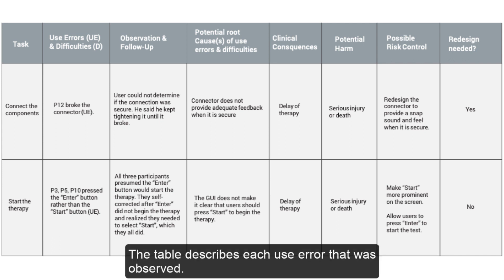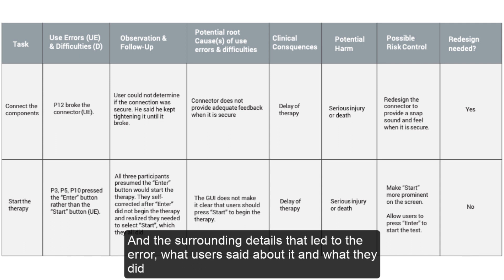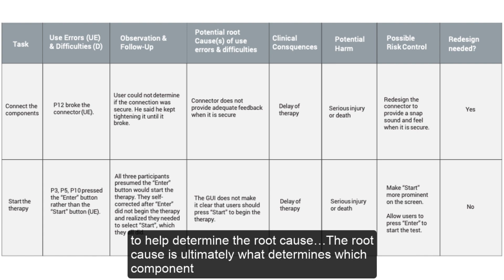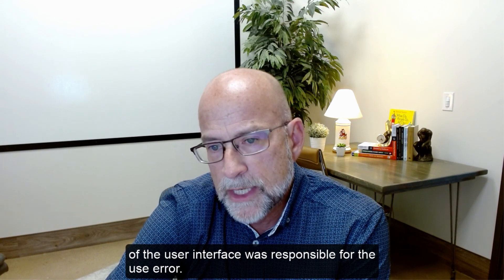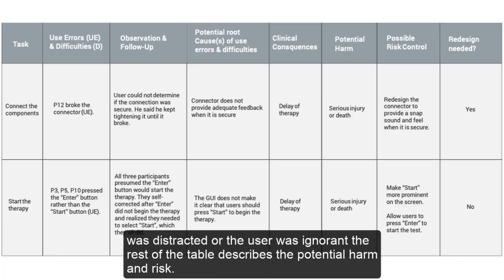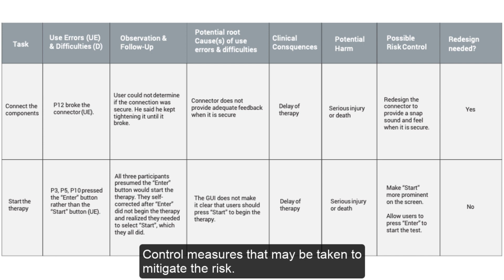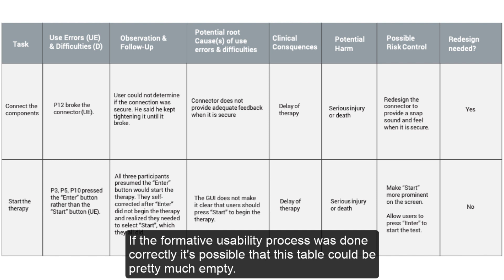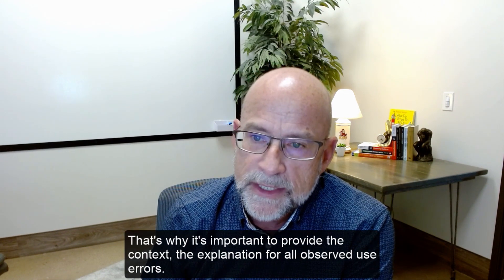Performance, knowledge, and qualitative data are analyzed and compiled in a detailed results table. The table describes each use error observed and the surrounding details — what users said and did — to help determine the root cause. The root cause determines which component of the user interface was responsible for the use error. The root cause should never be something like 'the user wasn't paying attention' or 'the user was ignorant.' The table also describes potential harm, risk, and control measures to mitigate the risk. If the formative usability process was done correctly, this table could be largely empty. However, a use error on a critical task doesn't necessarily mean the device cannot pass muster with the FDA — it always comes down to the level of risk associated with the use error.